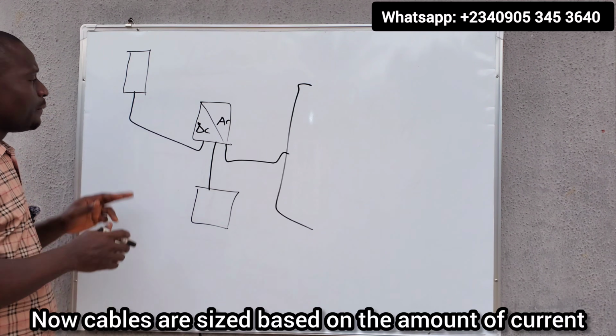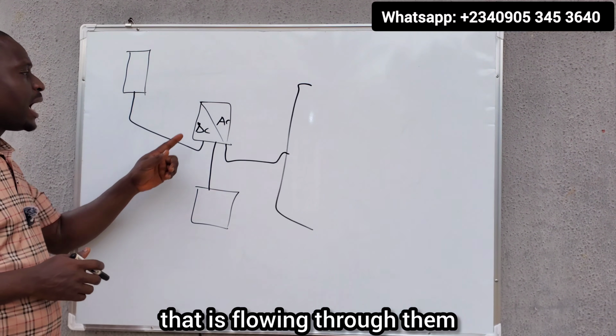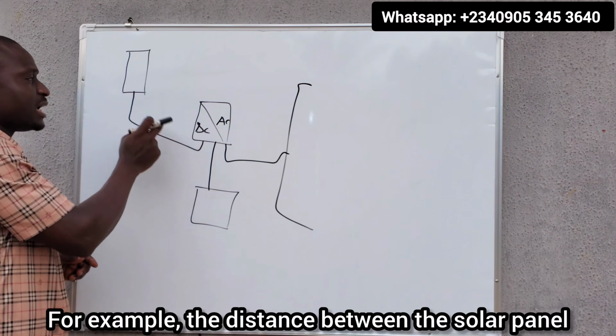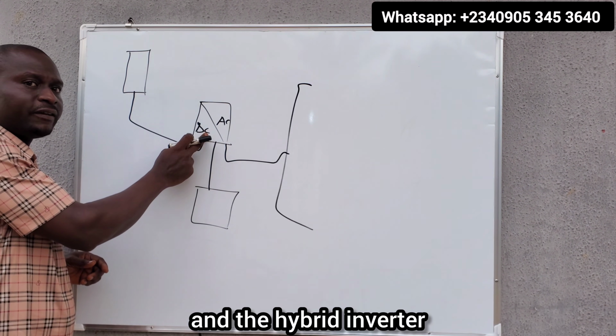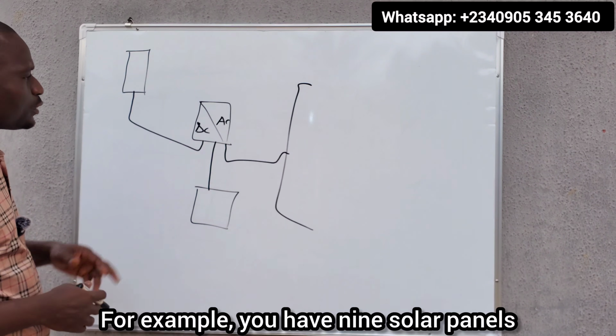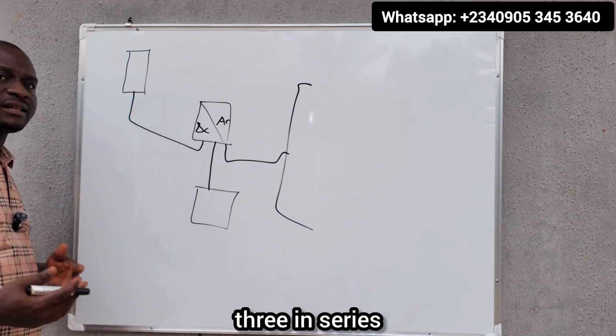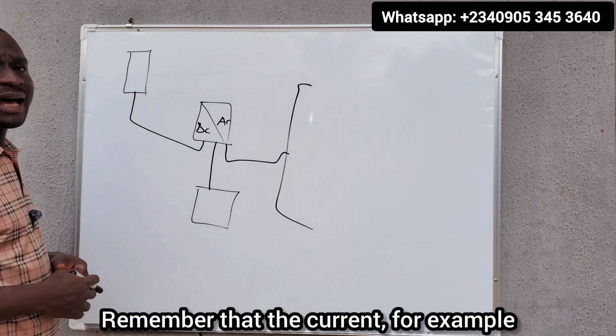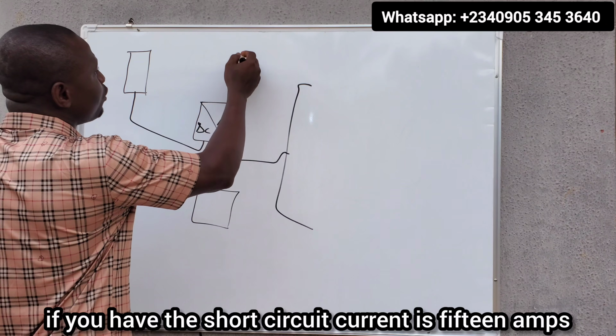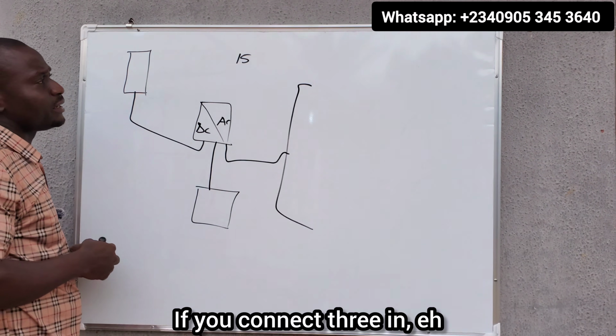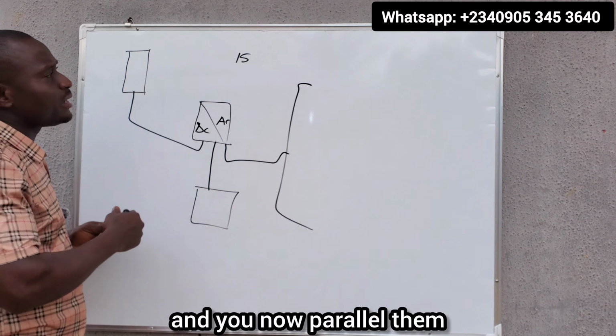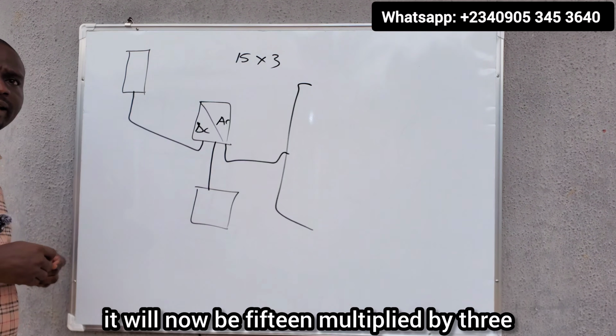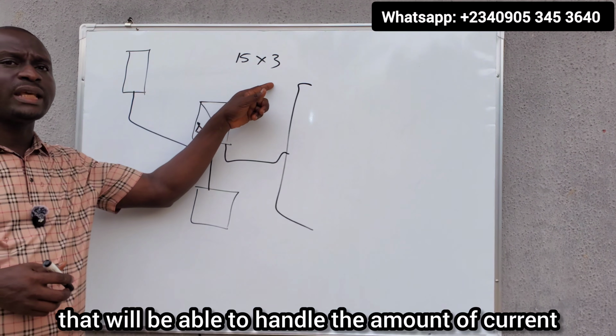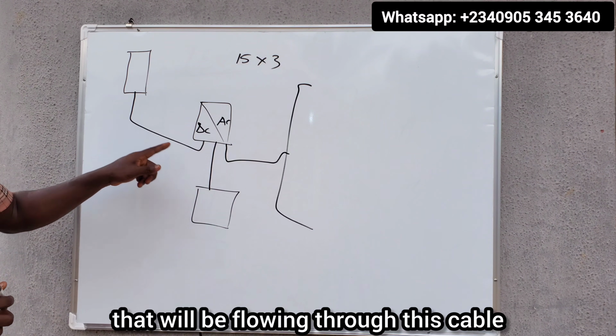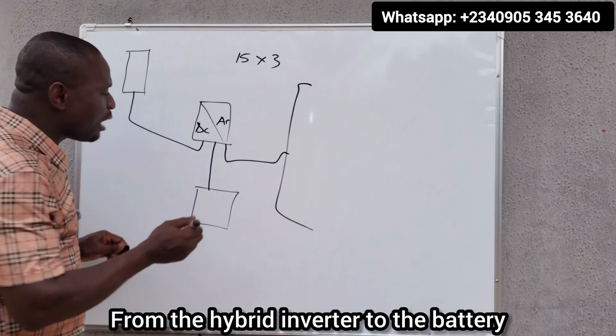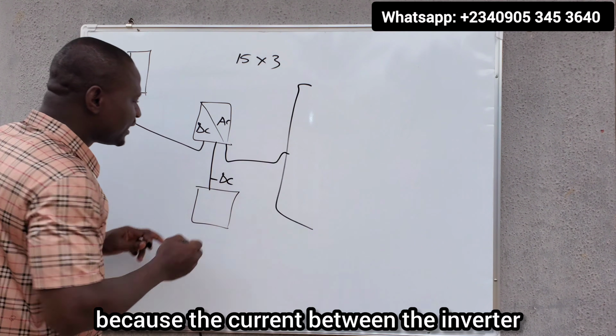Now, cables are sized based on the amount of current that is flowing through them and the distance. For example, the distance between the solar panel and the hybrid inverter. For example, you have 9 solar panels. You connect 3 in series, 3 in series, 3 in series, then you connect them in parallel. Remember the current, for example, if the short circuit current is 15 amps, and you connect 3 in series and now parallel them, it will now be 15 multiplied by 3. Now, you need a cable that will be able to handle the amount of current that will be flowing through this cable.